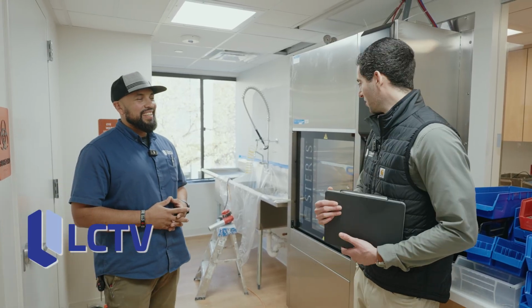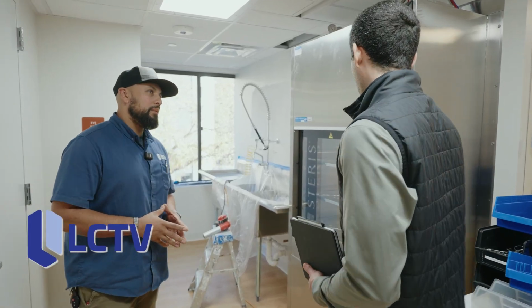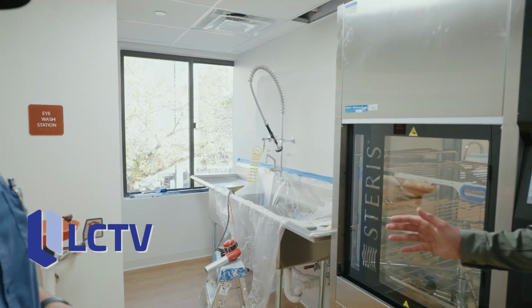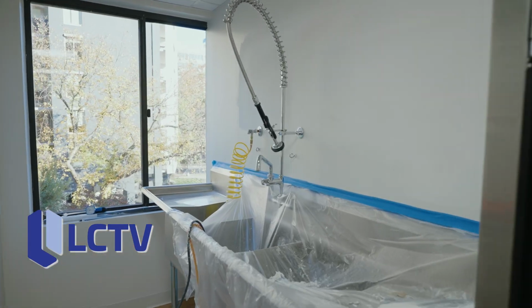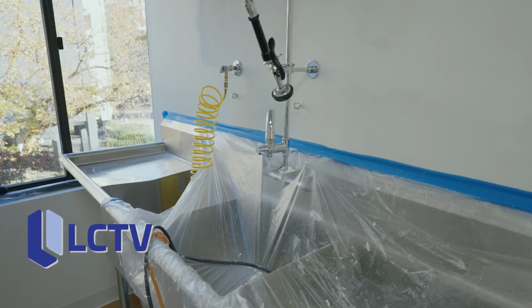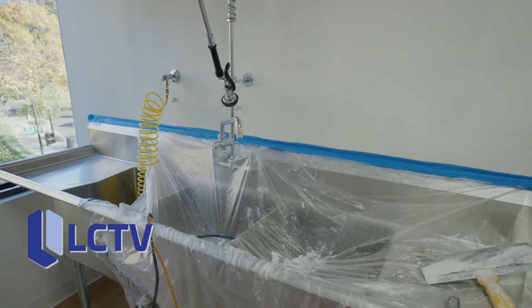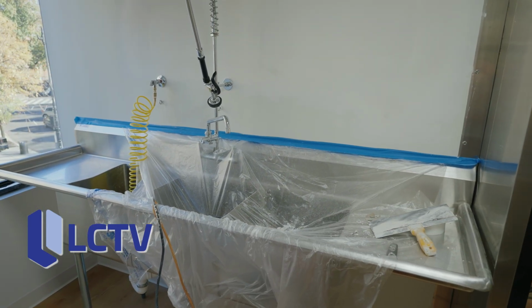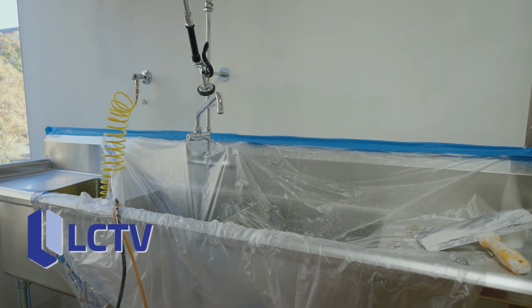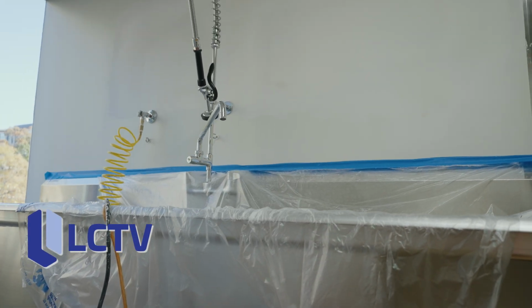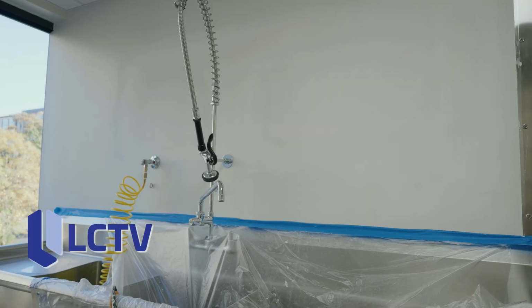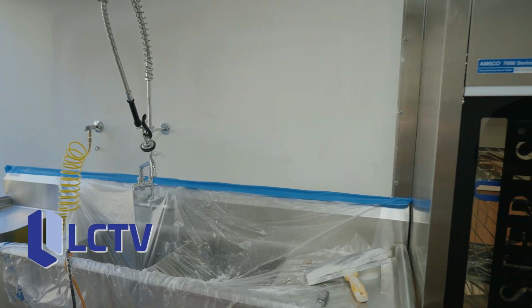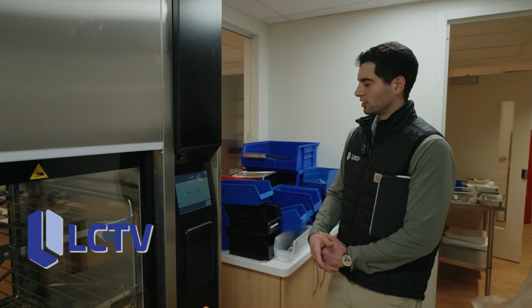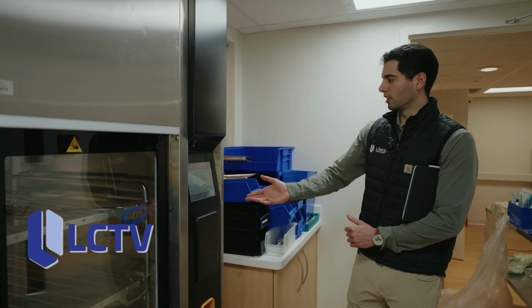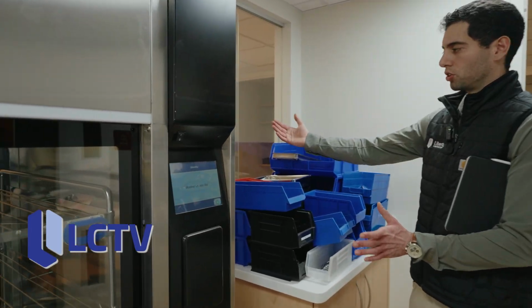Yes. So for this sink, for example, we knew that first is the option of, FGI will ask, do you have a separate clean and dirty side? You technically can have exemptions to have sterile and decontam in the same room, but you'd have to express that there are limitations that require that. For us, we didn't have enough space to separate clean and dirty, and this little pass-through system was pretty creative to make the most use of these two rooms, one on each side of the other.